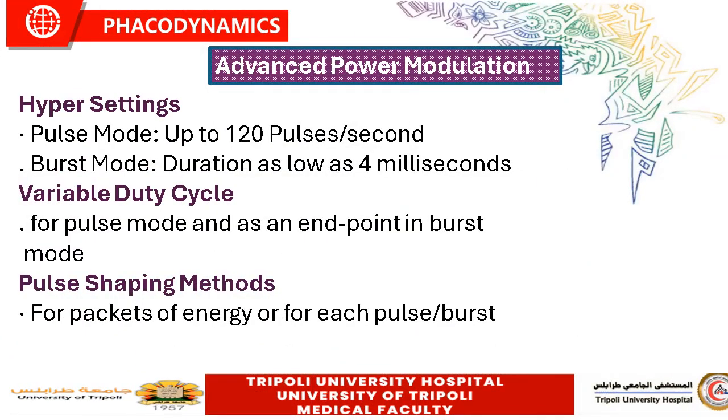Although the innovations of the modulation of the phaco power by the development of the pulse and burst mode, and further understanding of the role of the duty cycle in the absolute phaco time and the total dissipated energy delivered, doctors became able to address some of the drawbacks and disadvantages of the continuous pulse phaco.